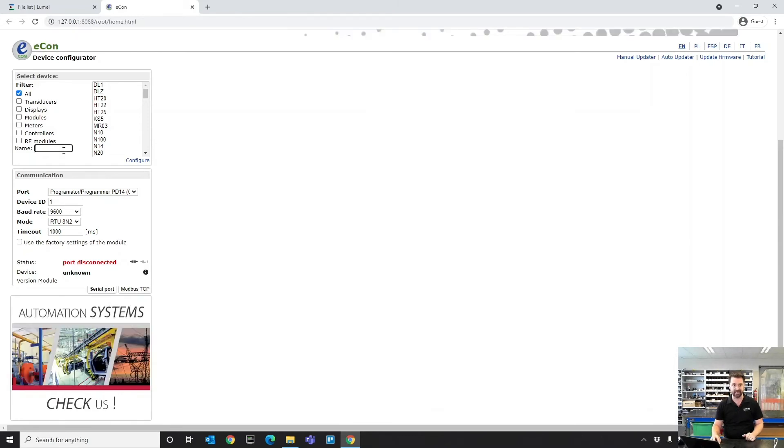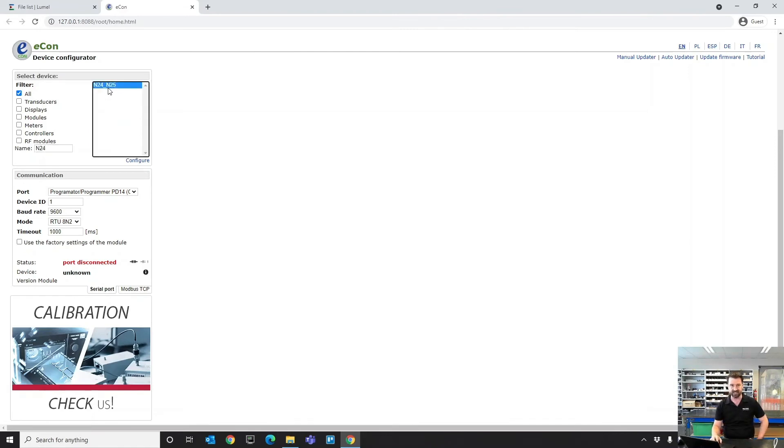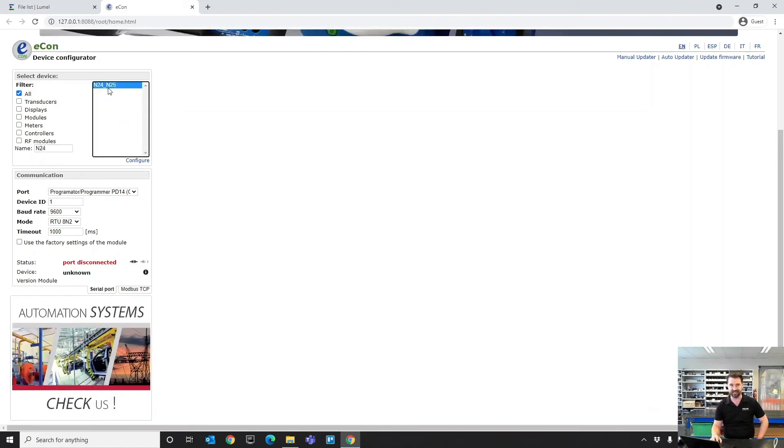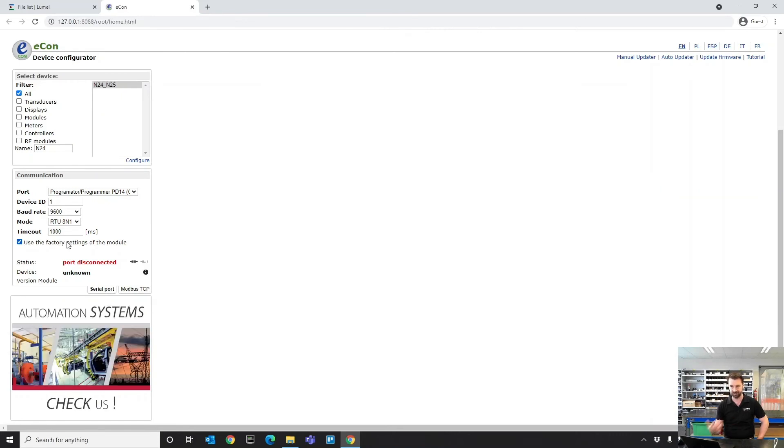When you're in here, say I'm trying to program an N24 display, I would type N24 in the filter. I'd find in there the right settings. A really useful thing to do is just tick this little checkbox here, which uses the factory settings for the serial communication for that device.